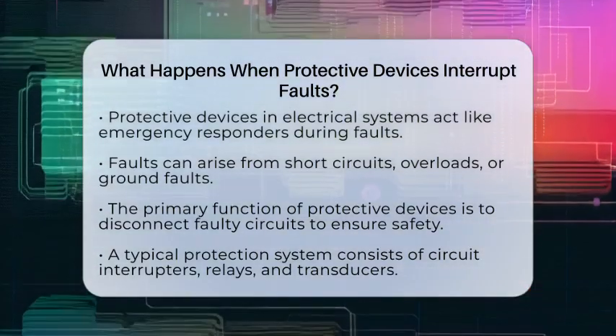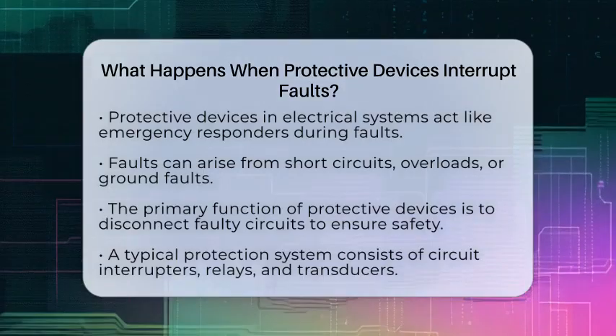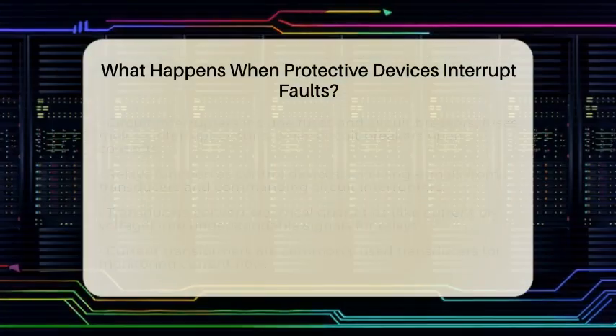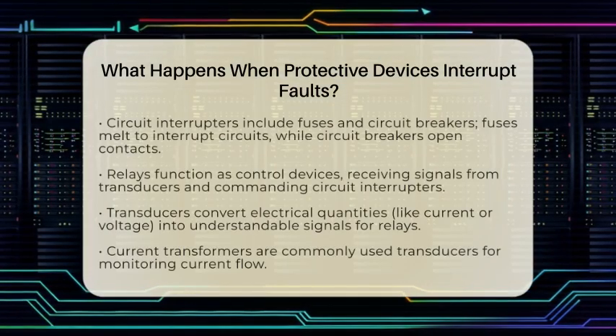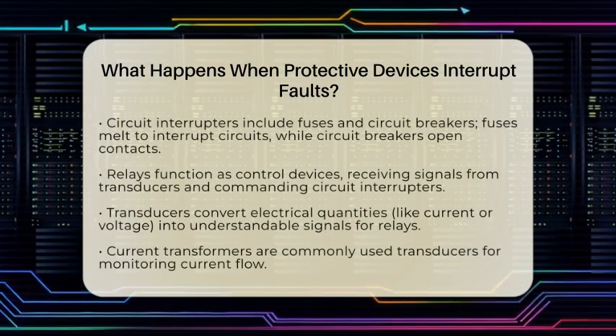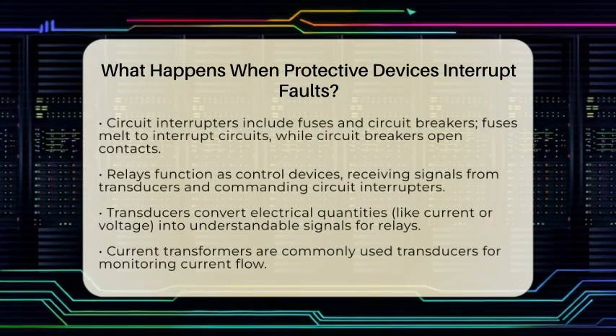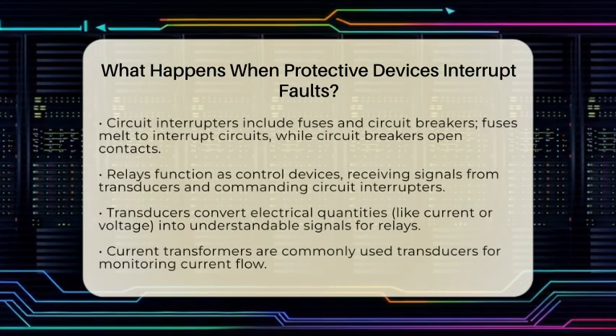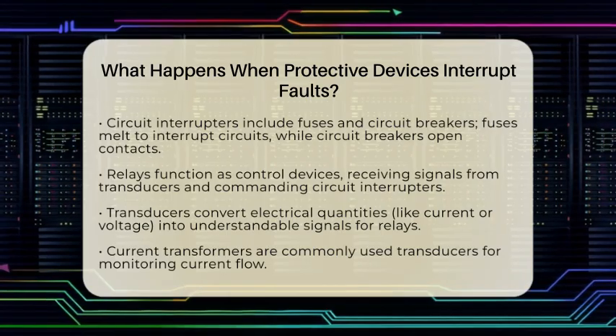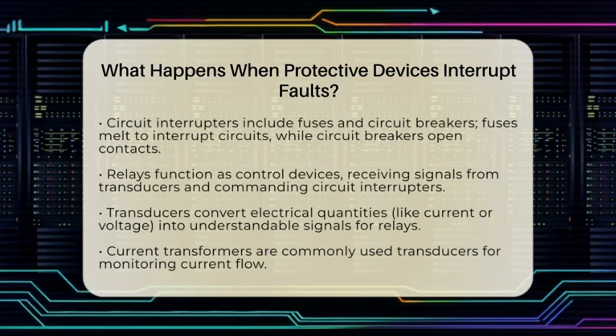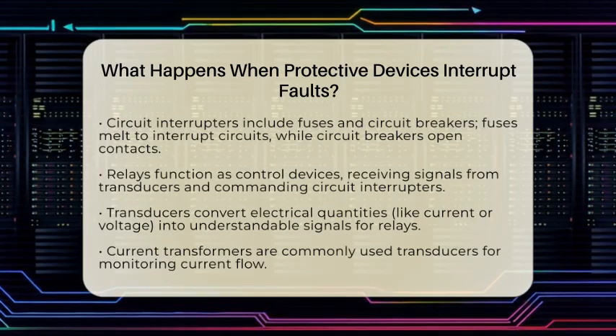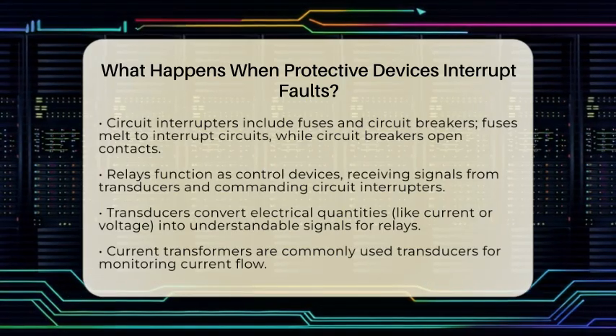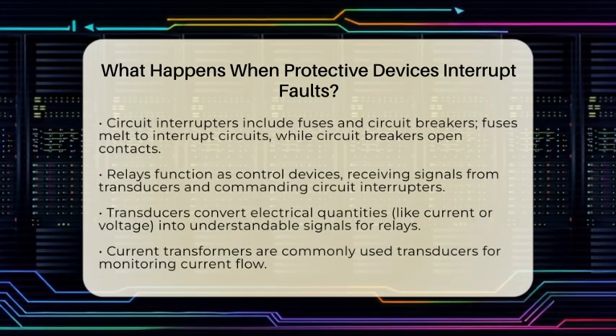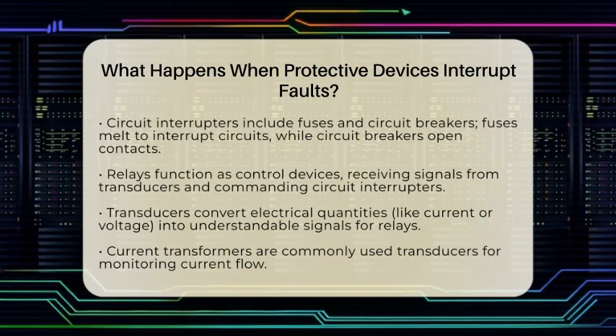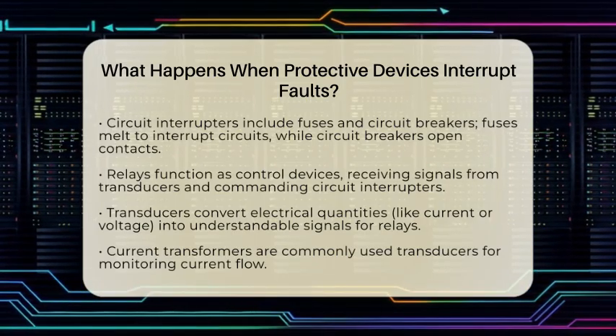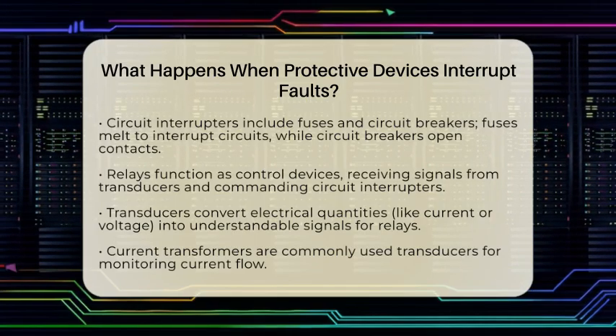Fuses are often used in distribution systems and melt when the current exceeds a certain limit, interrupting the circuit. Circuit breakers are more versatile and can be used in both distribution and transmission systems. They work by opening their contacts to break the circuit. Relays serve as control devices that receive signals from transducers and send commands to circuit interrupters to open or close. They are essential for ensuring that the interruption process is initiated quickly and accurately.